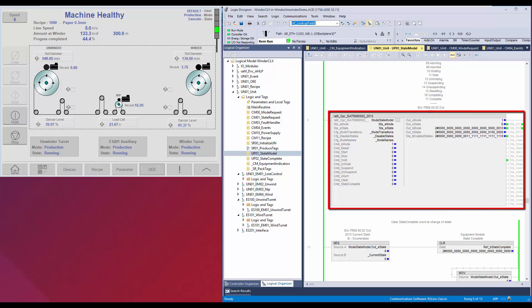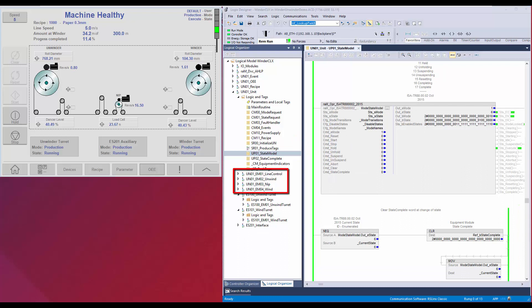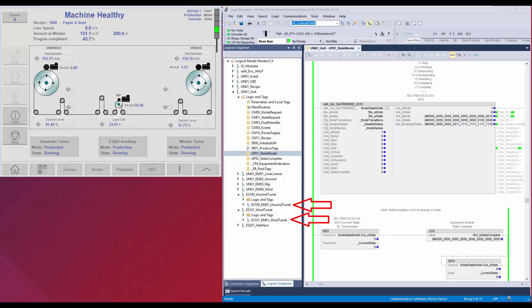In the state model instruction, the user can configure up to 31 modes. This parameter is to configure the states where mode transition is allowed. This parameter is to enable the states for each mode. This parameter is to enter the mode name. The equipment module programs for line control, winder, and unwinder are here. This is the equipment supervisor program for winder turret and unwinder turret. Under each of the equipment supervisors are their respective equipment programs.